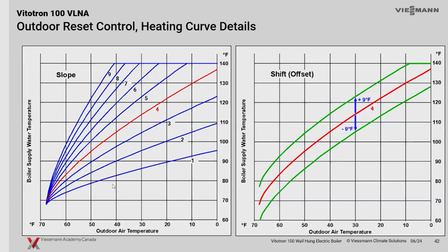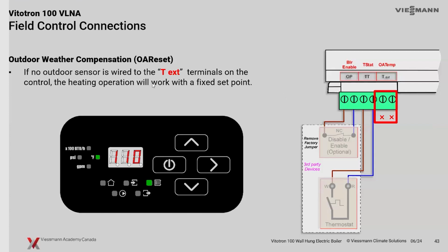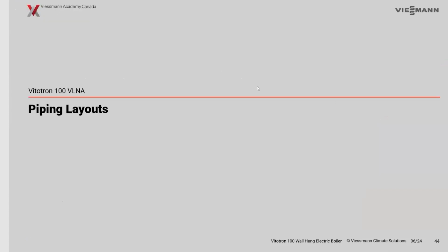It's very similar to what we have in our current Vitodens line and Vitocrossal line of gas-fired boilers. Instead of the actual curve itself, they number them 1 to 9. Then we have a shift or offset, so we can do a parallel adjustment of the heating curve as well. So there are some customization capabilities on these heating curves. And if the outdoor sensor is not installed, you're going to operate off a fixed set point. If you put the outdoor sensor on, it automatically switches to a heating curve for your use.